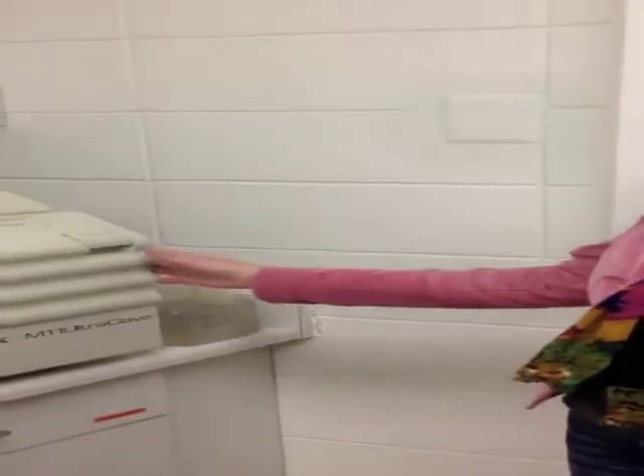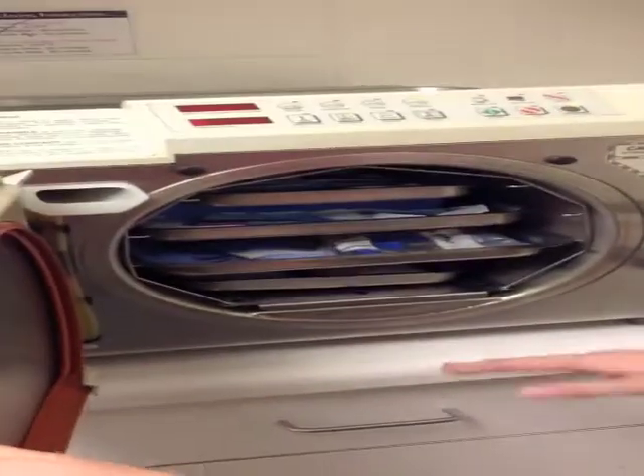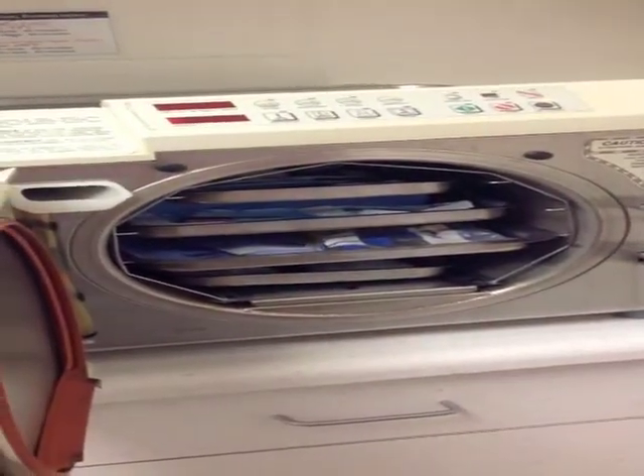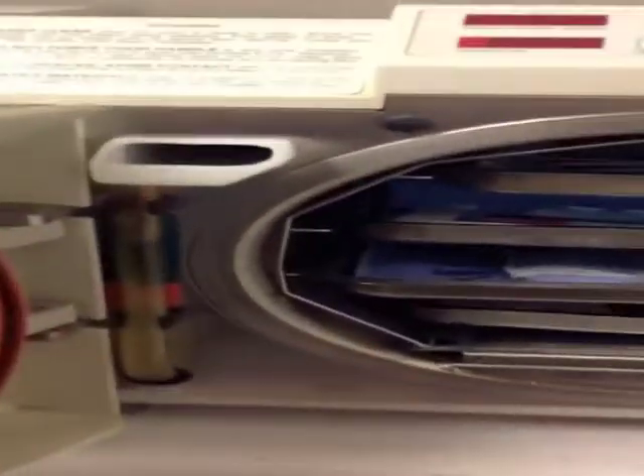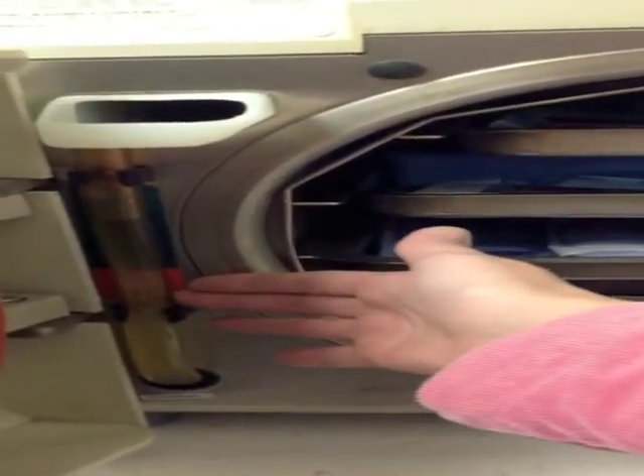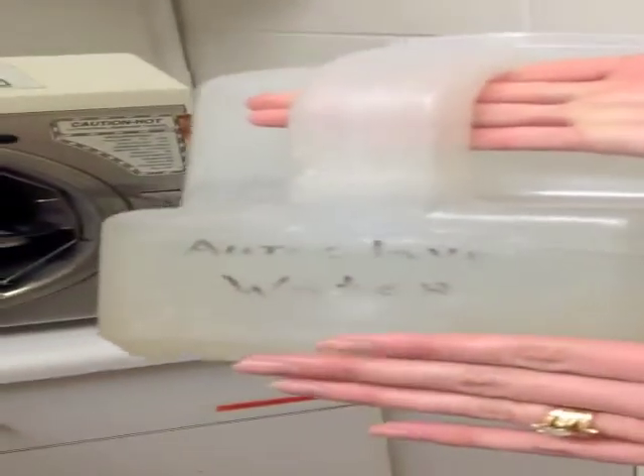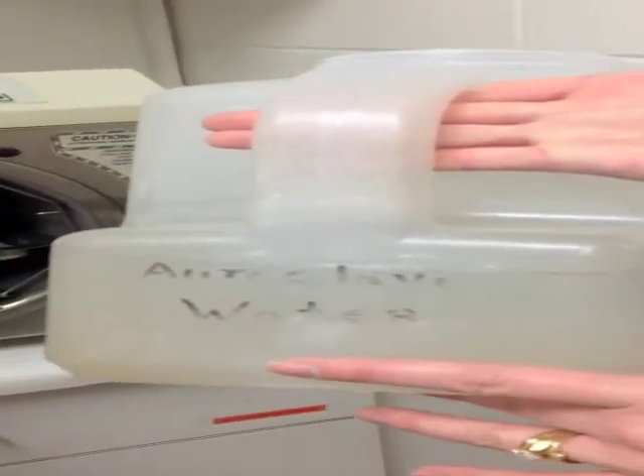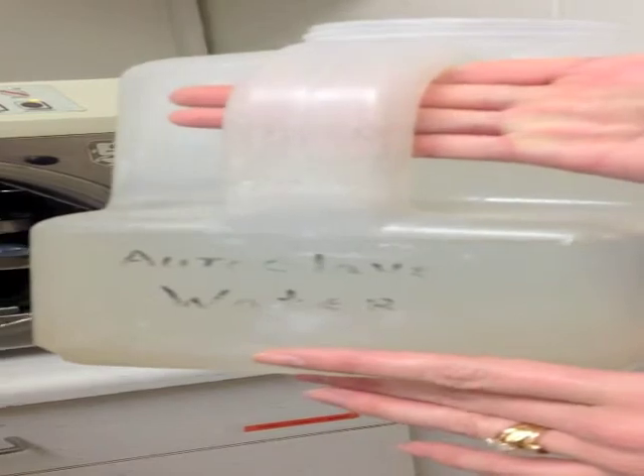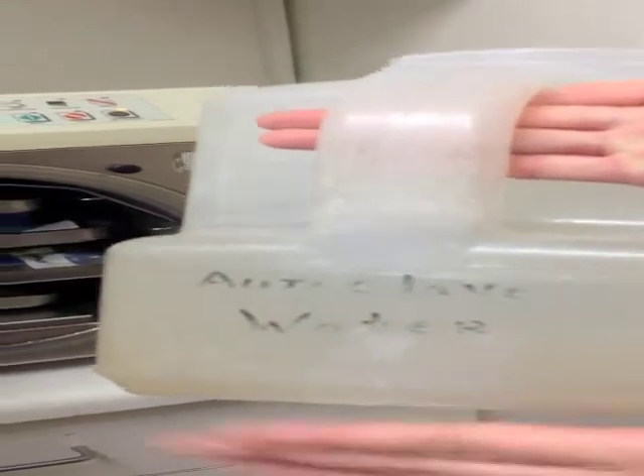When loading the autoclave, the one thing you want to always make sure is that the water level is always in the green and not in the red. The water can be found typically in the jugs that are sitting next to the autoclave. This water is specific for the autoclave. It's the distilled water.